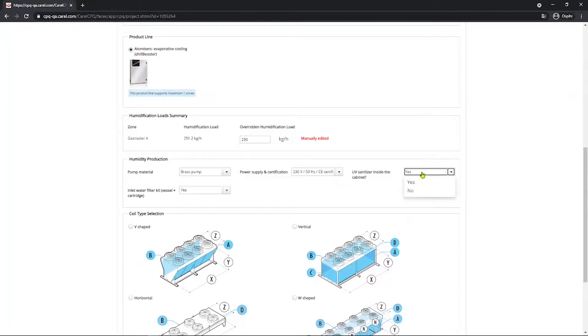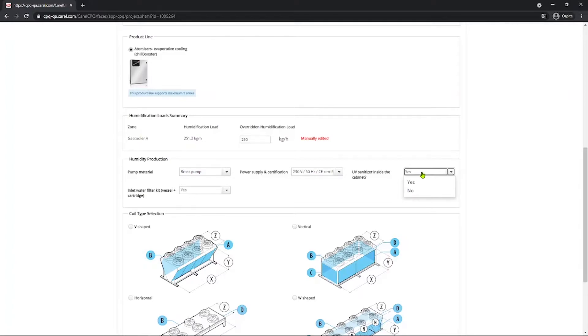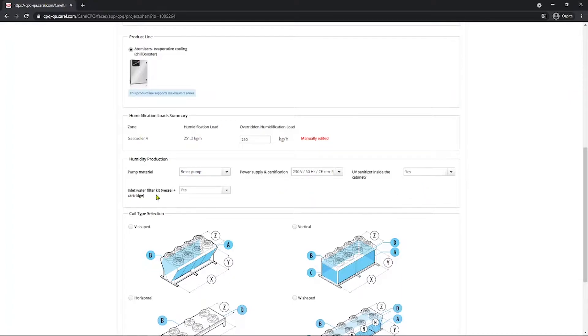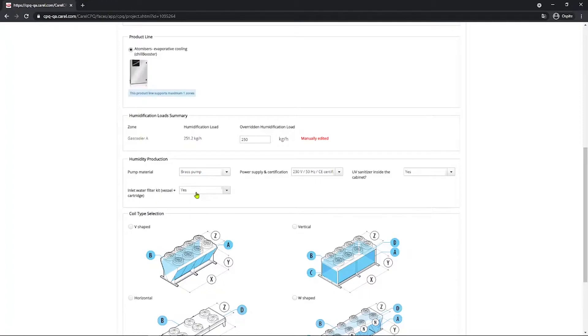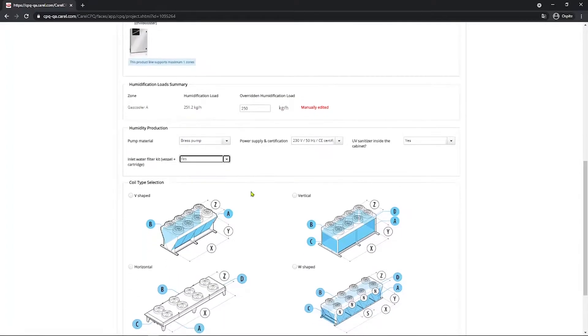UV disinfection and sanitizer inside the cabinet. For reason of hygiene, the customer may be requesting the installation of a UV lamp to destroy any bacteria that may be present in the water that's sprayed. So let's say yes or no, depending on the request of the customer. In this case, maybe yes. And the inlet water filter kit, vessel plus cartridge. This is recommended to prevent debris and impurities from entering the cabinet water circuit. So in this case, select yes.